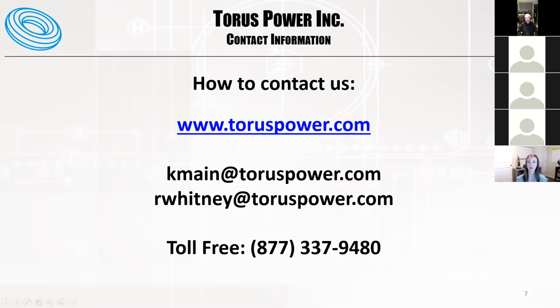You bet. One thing I can add, Mark, is when you're getting into a larger system for somebody who's an audiophile, the load requirement may far exceed 20 amps. When you're saying put in a 20 amp or 30 amp circuit, we see projects where we're putting in 100 amp feeds to the audio gear, or even beyond that. So it could easily be that the equipment demands much more than 20 or even 30 amps, and Ross can help guide you on that.